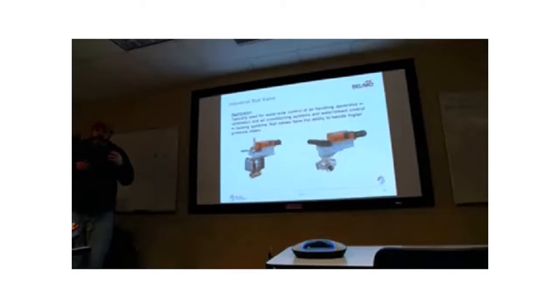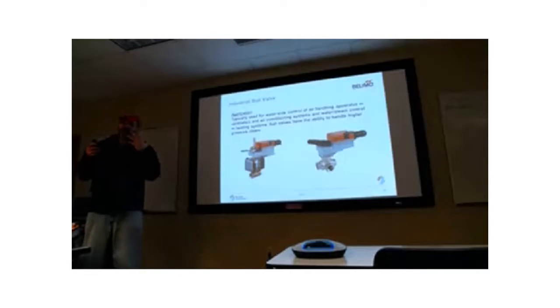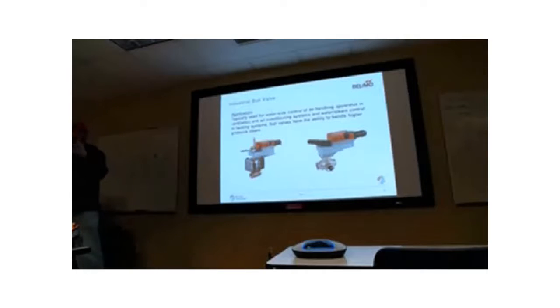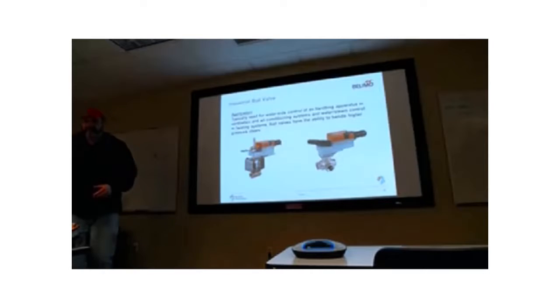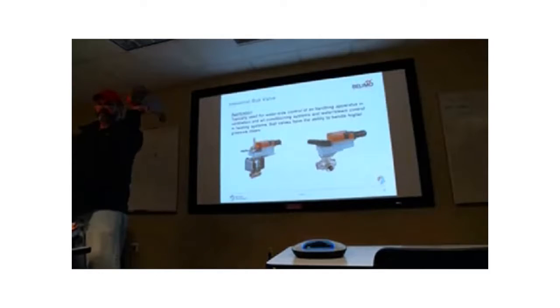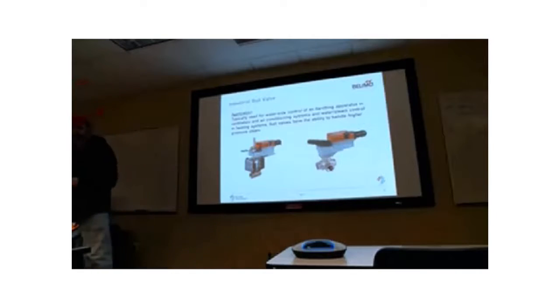There are only so many valves suited for that purpose, because most of the valves I've shown you so far are meant to be in closed systems, right? They're going to be wet on both sides, water on the upstream side, water on the downstream side. This ball valve can take what we call open-end service, where you can have it connected to atmosphere and you're not going to blow out or damage the valve. If you get into that kind of situation, be careful on the type of valve you choose.